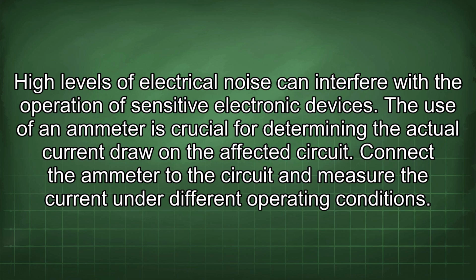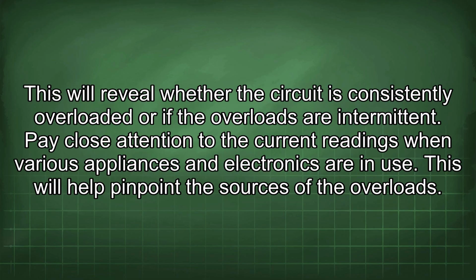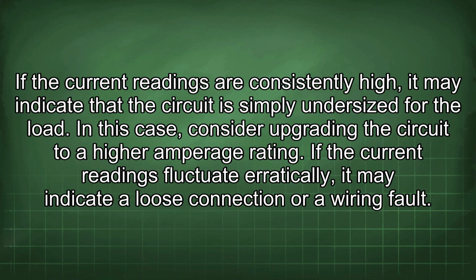The use of an ammeter is crucial for determining the actual current draw on the affected circuit. Connect the ammeter to the circuit and measure the current under different operating conditions. This will reveal whether the circuit is consistently overloaded or if the overloads are intermittent. Pay close attention to the current readings when various appliances and electronics are in use. This will help pinpoint the sources of the overloads. If the current readings are consistently high, it may indicate that the circuit is simply undersized for the load. In this case, consider upgrading the circuit to a higher amperage rating. If the current readings fluctuate erratically, it may indicate a loose connection or a wiring fault.